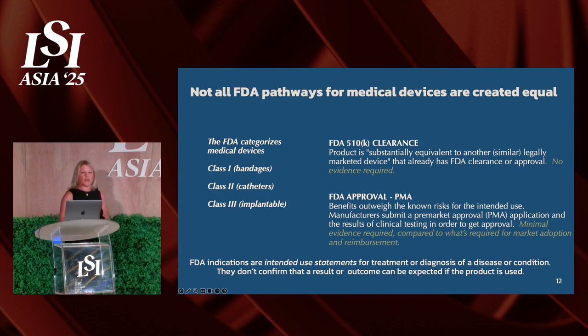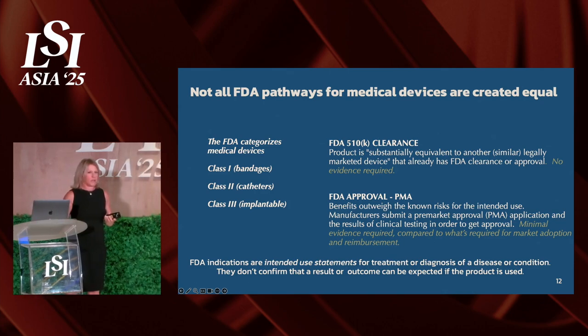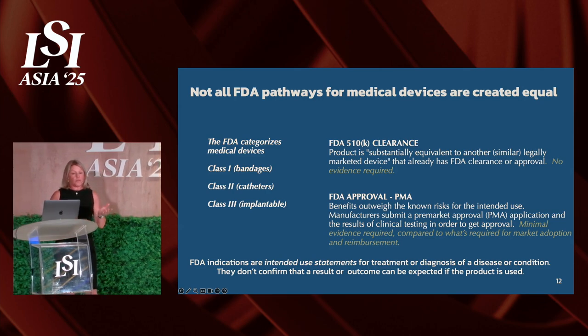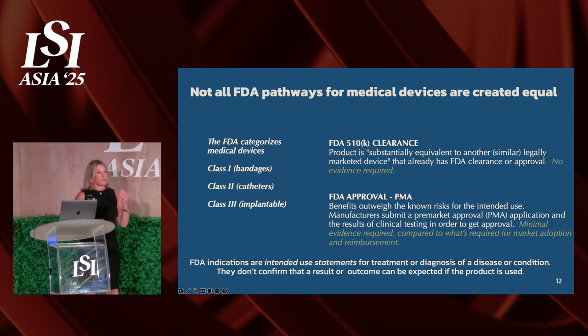So understanding that with 510(k) clearance, you don't need any clinical data. You need bench data, essentially, right? You find a predicate and you get cleared and you're on the market. De novo 510(k) clearance is a little bit different. There's no substantial risk, there is no predicate, and you're on a little bit of a faster track with a 510(k) de novo. And then you have PMA approval. That's premarket approval. You have to do rigorous studies for class 3 devices. But really understanding how these different FDA pathways impact your technology is going to be critical.